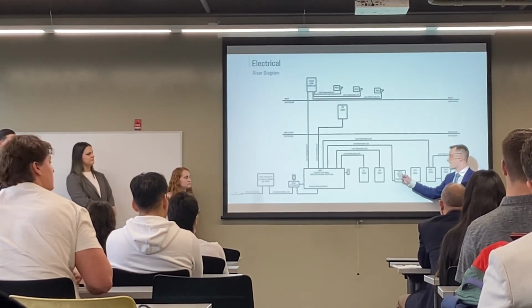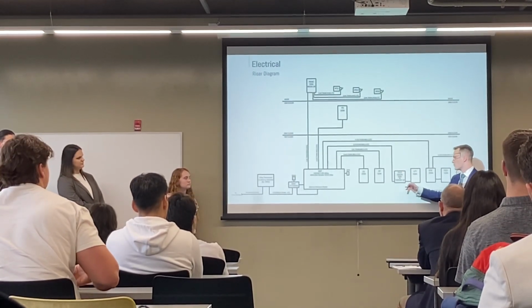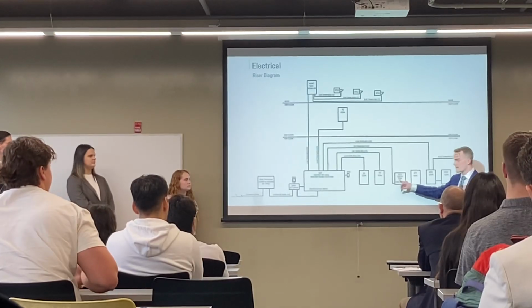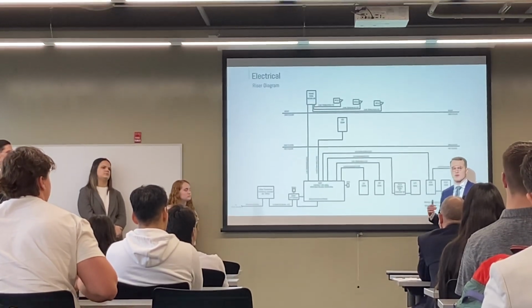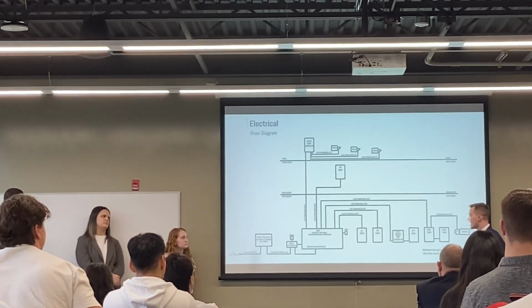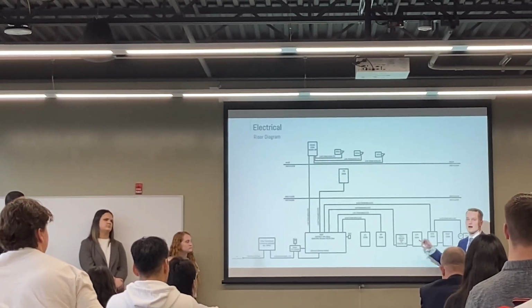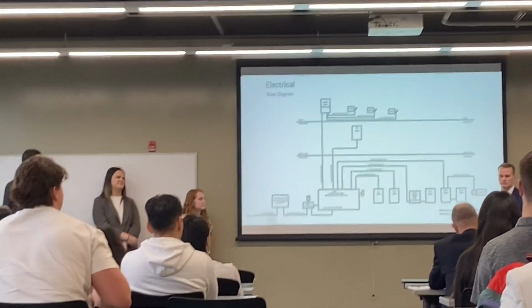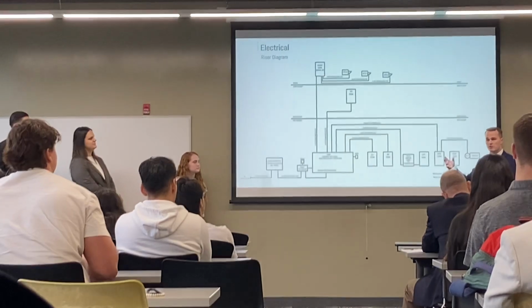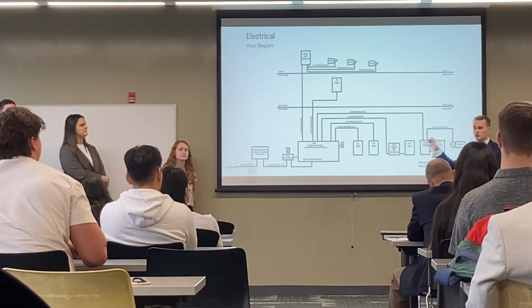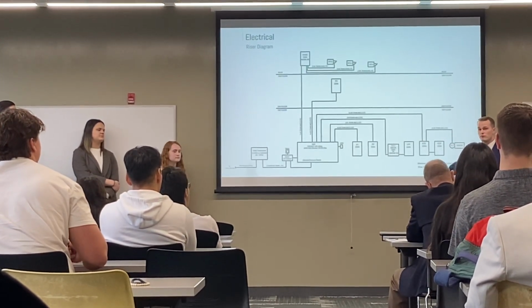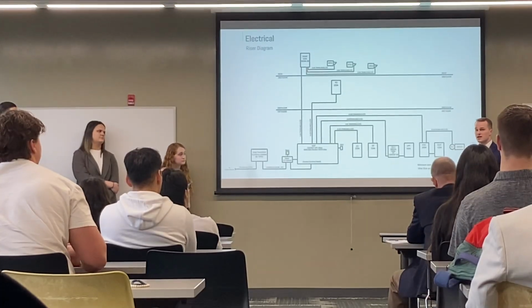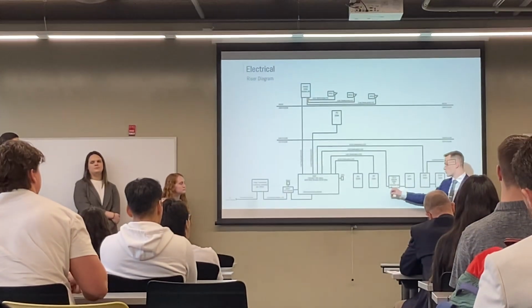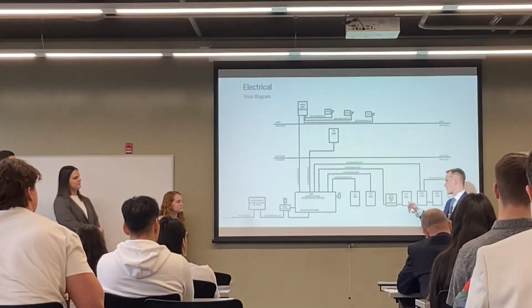Then we come over here to TX1, which is a step-down transformer, and that's 30 kVA, 208 volt. We have to drop that down to 120/240 single phase, and the reason is on LP1, the faculty, or Brian, he requested 2 tour bus plugins for when a tour bus comes and also the golf cart, but they are 240 volt, 50 amp split phase. So we have to drop that to 120/240 single phase to be able to power those properly.